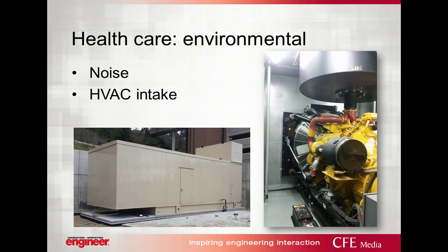The physical location of the generator will inevitably drive the noise attenuation requirements for that genset and maybe even the building facade. Another factor that we need to consider, regardless of occupancy type, but of specific interest to healthcare, is the proximity of the generator exhaust to the building HVAC intakes. Exhaust smells are not pleasant, and if those smells come into an operating room or patient room, you can expect to have a very upset client.